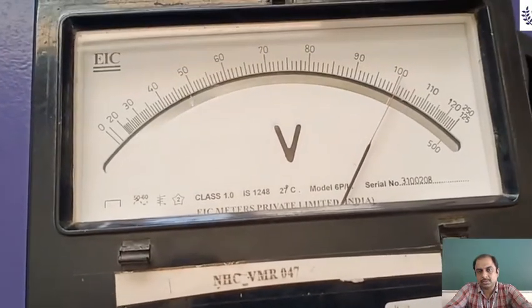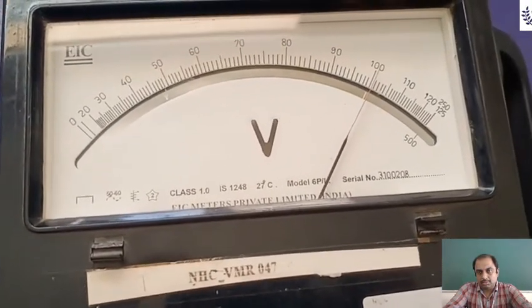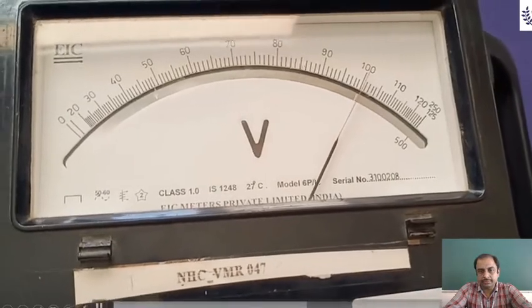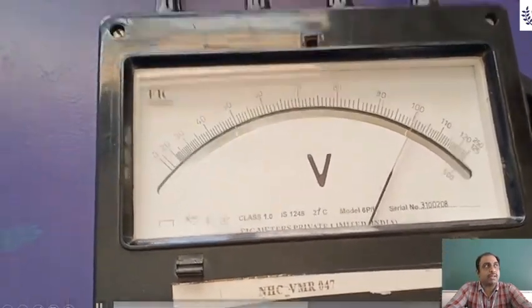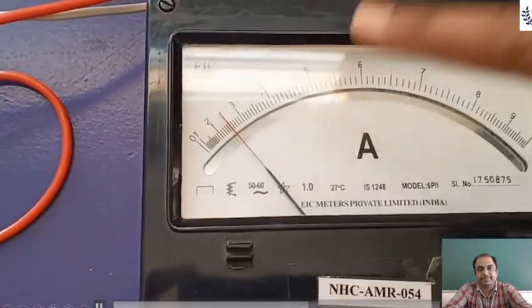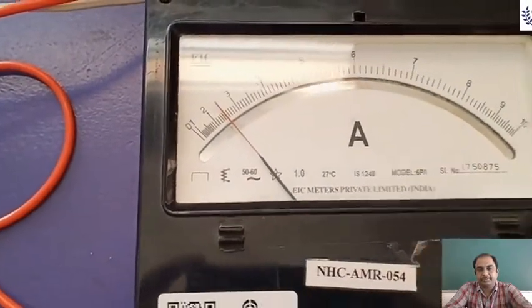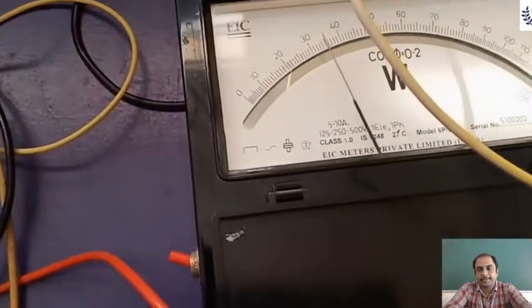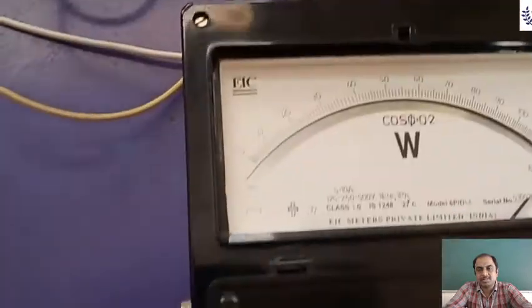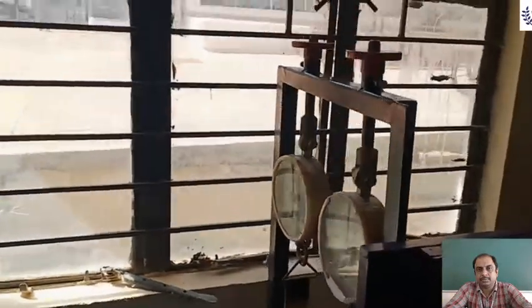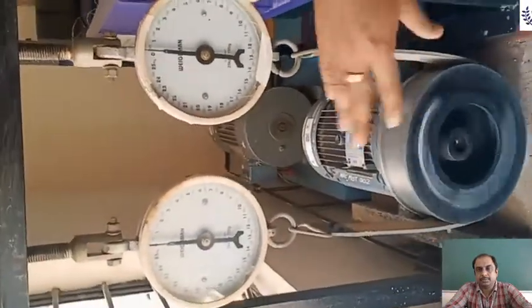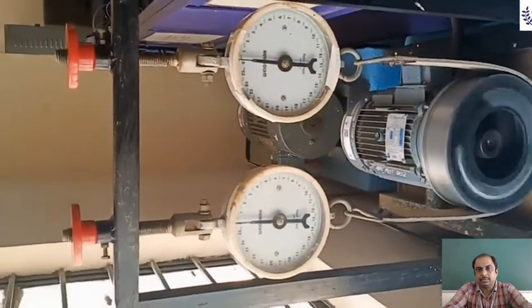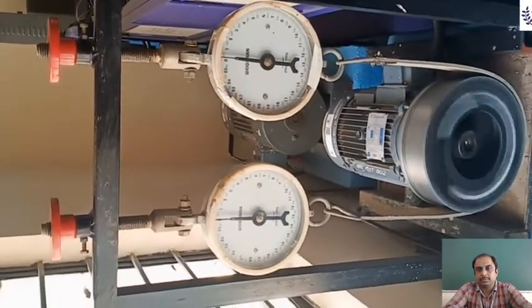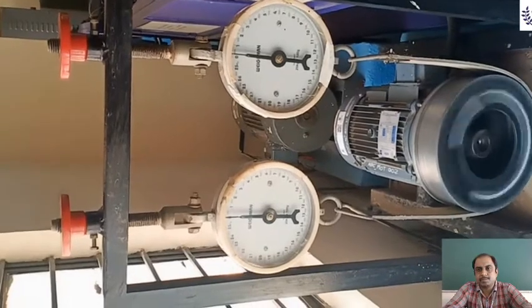This is the meter. The main specification of the meter is 500 volt, so we can fix it at 400 volt. You can see the current and W1, W2. Now in the motor, we are not applying the load, so it is free. This is the no load test. When we are not applying the load, the machine is free to run.